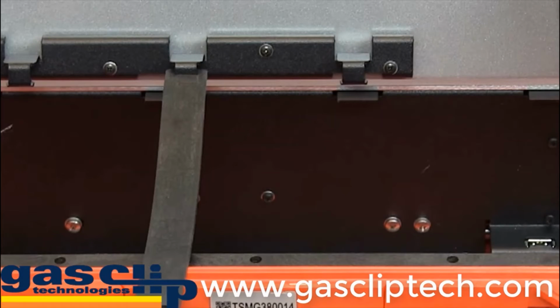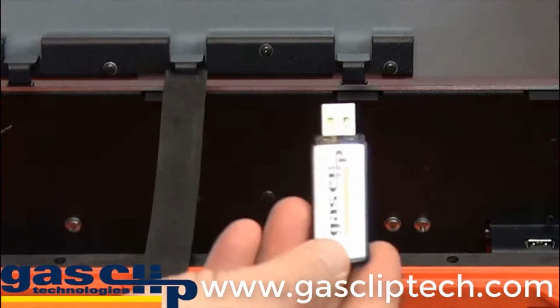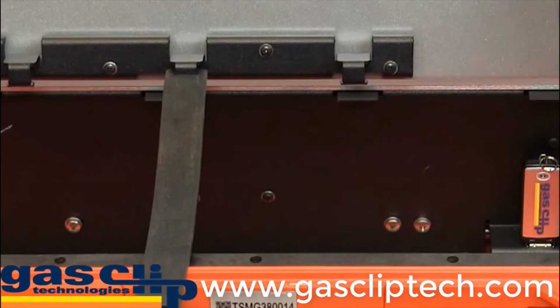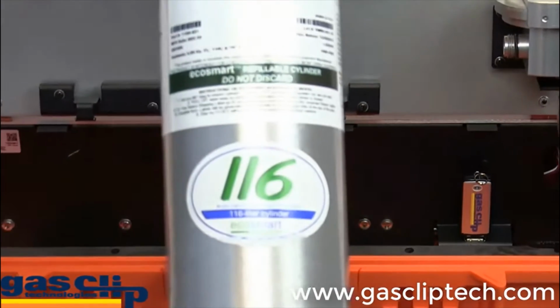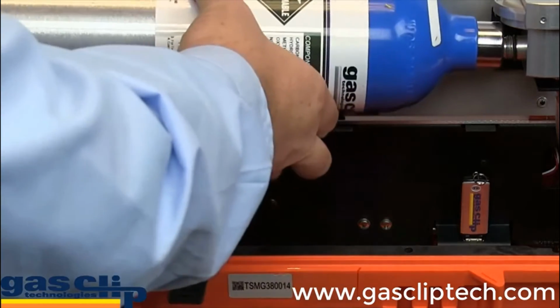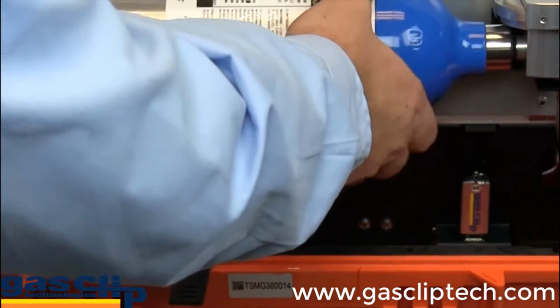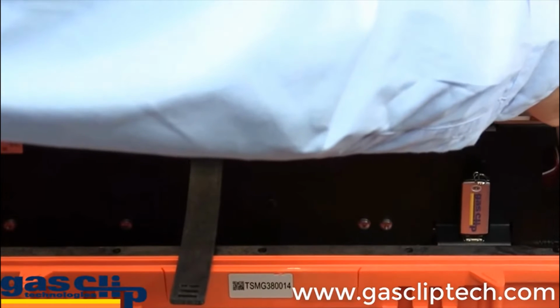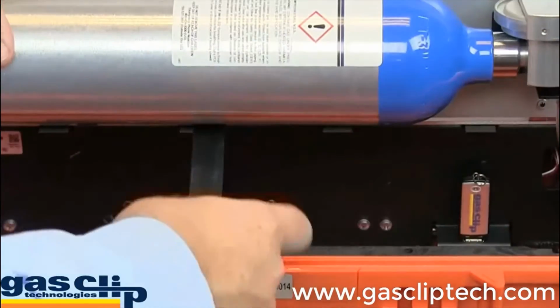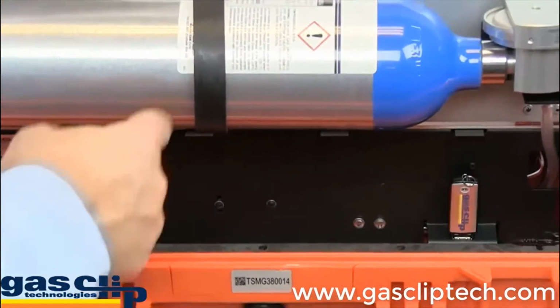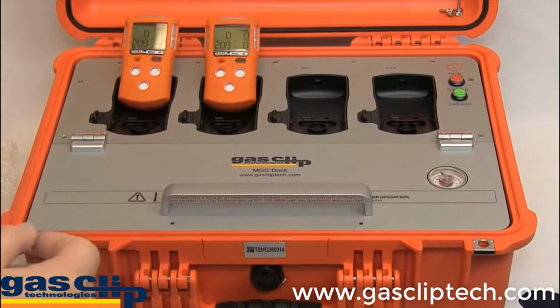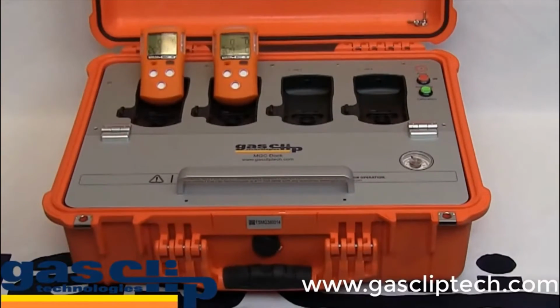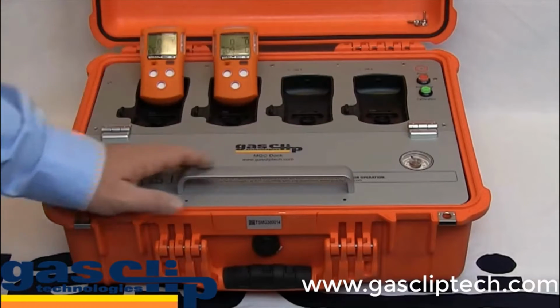To calibrate or bump test using the MGC dock, simply place the provided USB flash drive in the associated port. One bottle of good calibration gas gets screwed onto the regulator. Once snug, secure the bottle with the provided bottle strap. Close the lid and we're ready to test. Bump testing monitors with the MGC dock could not be any easier. You can test anywhere from 1 to 4 monitors at the same time.